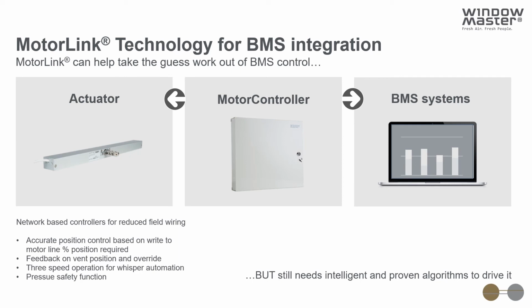It gives the BMS the opportunity to send groups of actuators to very specific positions on a percentage basis, 1%, 2%, very accurate control, and get position feedback from the actuators to confirm that they've arrived there, they're healthy, and they're happy. They'll also get feedback if the vent's been overridden. During those automated operations, the BMS can tell the actuator to operate very slowly and almost silently in the background. However, if there is a more critical function, such as rain or smoke, then the BMS or the control system can tell the actuators to operate much more quickly to protect the building and the occupants.